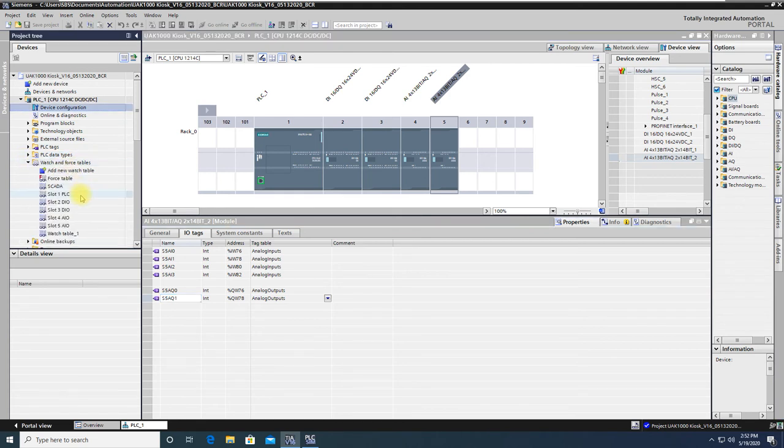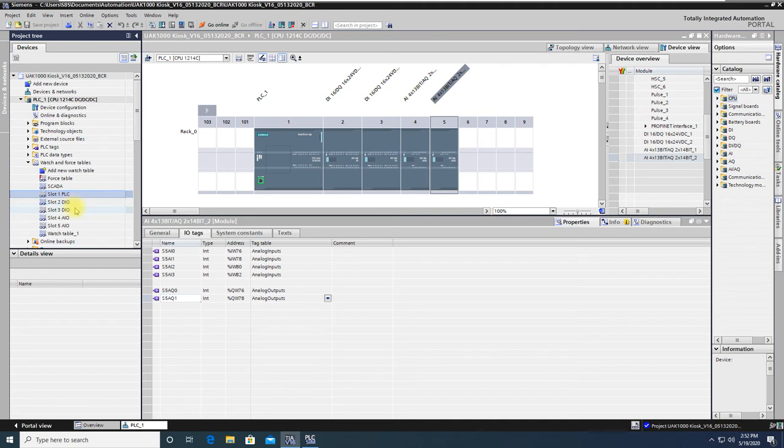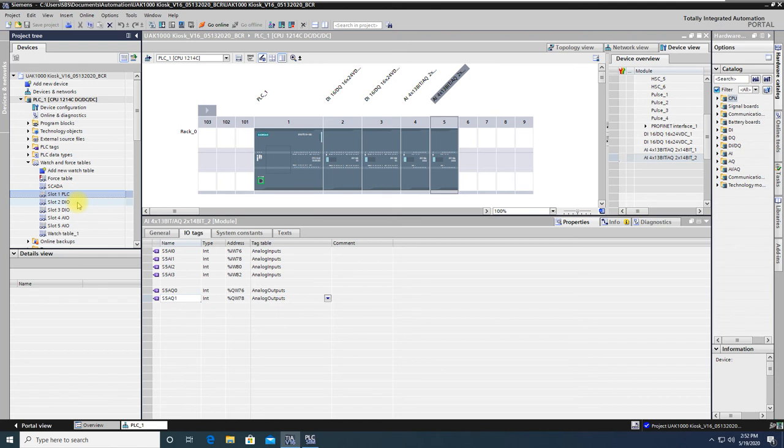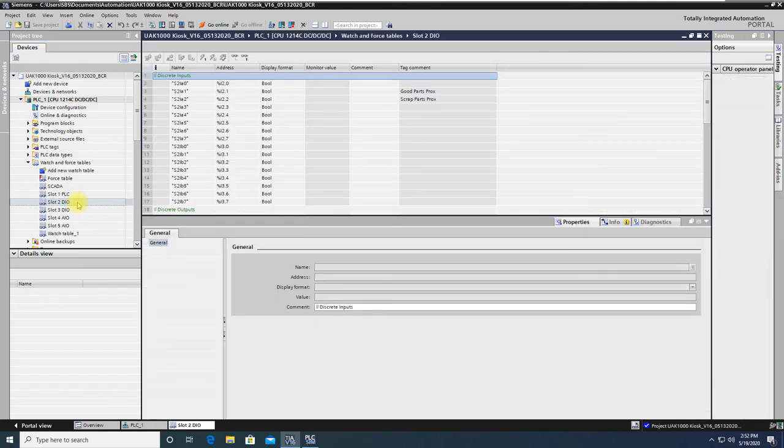So in troubleshooting, you should be able to pick any of the IO in the PLC, or slot 1, any of the IO in slot 2, 3, or 4, or 5, and be able to see what's going on with that IO. Let me just pick here something about slot 2, with its discrete inputs and outputs.